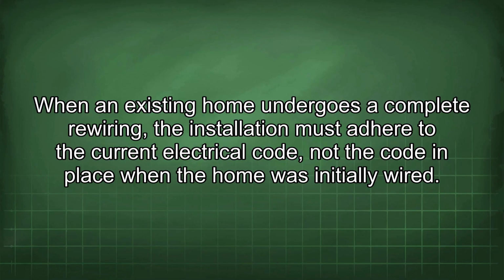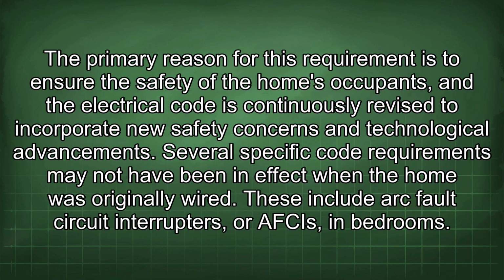When an existing home undergoes a complete rewiring, the installation must adhere to the current electrical code, not the code in place when the home was initially wired. The primary reason for this requirement is to ensure the safety of the home's occupants, and the electrical code is continuously revised to incorporate new safety concerns and technological advancements. Several specific code requirements may not have been in effect when the home was originally wired.